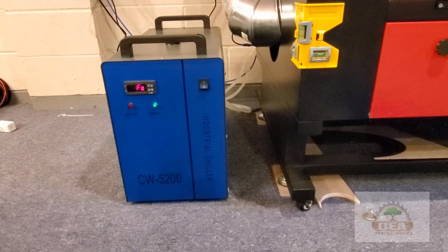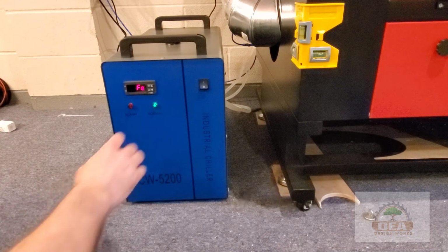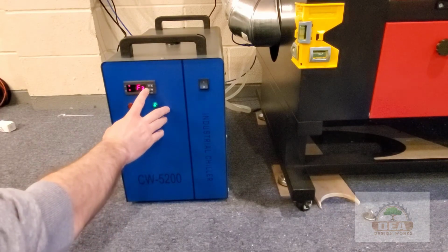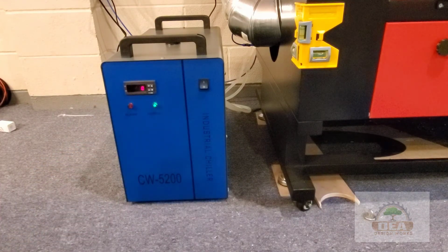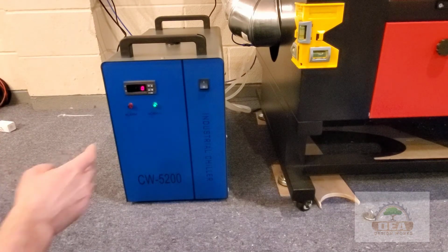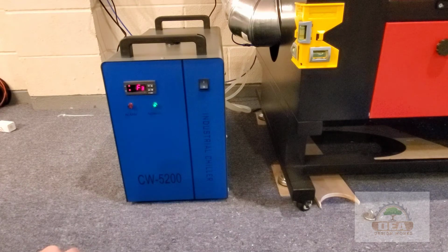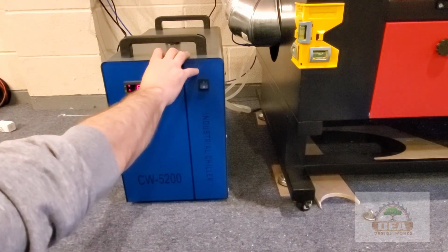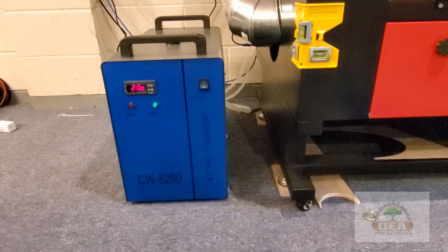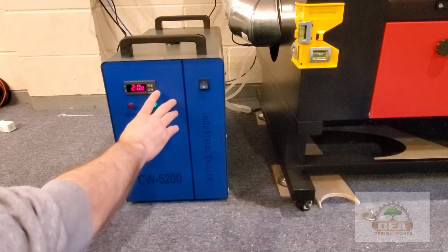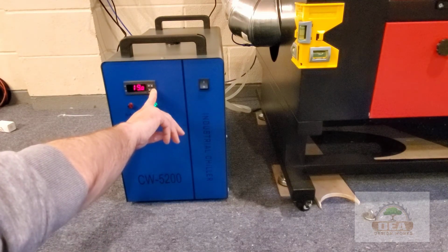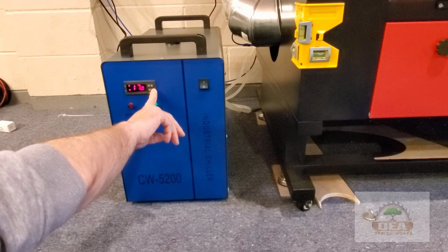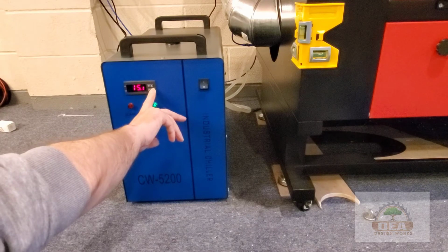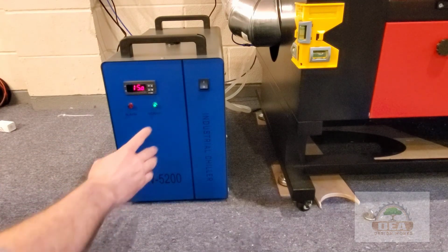And by doing so, I see F0 on the screen. So I'm going to want to change to F3. And I'm going to press set. And I want to go to 0 here, which changes the mode from intelligent to constant. I go ahead and press set there. That brings me back to the F3. And then I want to go to F9. I'll press set here. And see, that one is showing 20 for me. So I want to change that. F9 is the lowest allowed water temperature. So I want to go down to 15 here because I don't want my water temperature to go any lower than 15 degrees Celsius. So I get it to 15 and I'm going to go ahead and press set there.